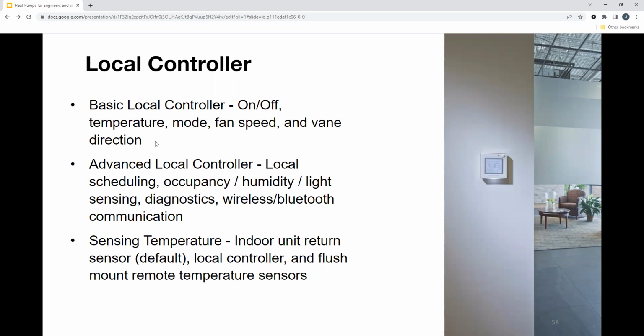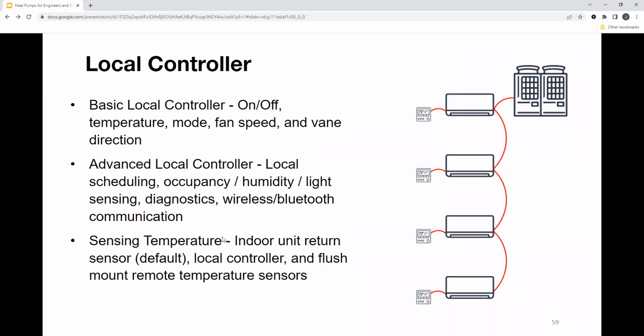There's also advanced controls. Maybe if you don't have a central controller that ties in all the equipment, maybe you select an advanced controller for scheduling purposes, right? A basic controller doesn't have that, but if you did want scheduling, you would be able to select one of these advanced local controllers. There's also options for occupancy sensing, humidity, light sensing, diagnostics. There's even wireless and Bluetooth communication. Right, so diagnostics, that's a great one. All of the fan coil units are going to be connected to your controllers. And if there is an issue, let's say you need to replace a filter, or there's a condensate float switch that's tripped, that will go with a code directly to the local controller. So it'll notify the occupants that the system is off and not working properly. Right, and this is a simple system that you can set up. You have your condenser, you have your fan coil units with a local thermostat in each zone. Pretty basic.